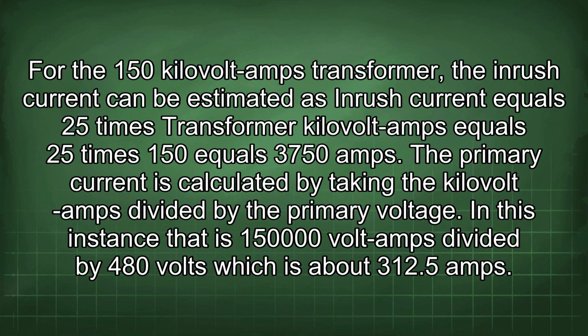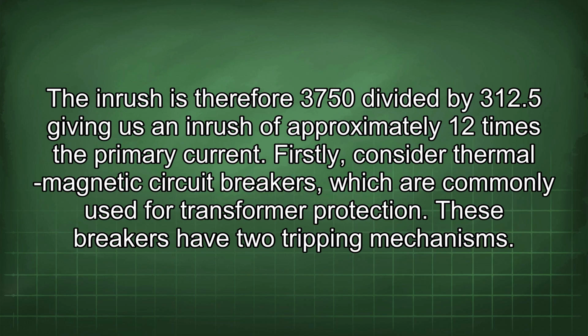For the 150 kilovolt-amps transformer, the inrush current can be estimated as inrush current equals 25 times transformer kilovolt-amps equals 25 times 150 equals 3750 amps. The primary current is calculated by taking the kilovolt-amps divided by the primary voltage. In this instance, that is 150,000 volt-amps divided by 480 volts, which is about 312.5 amps. The inrush is therefore 3750 divided by 312.5, giving us an inrush of approximately 12 times the primary current.